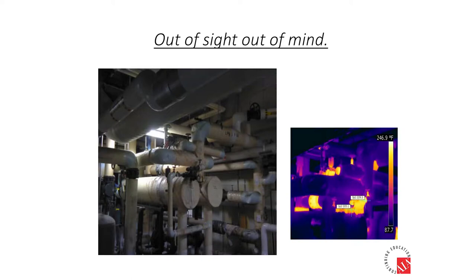And the reason I'm pointing this out is most of you people that have infrared cameras are walking around these rooms all the time. And if you walk around in these rooms and you see these bright yellow, white objects in a dark room, you know there's opportunity. And all these guys that are electricians that are walking around with infrared cameras, I say, look at other things while you're there. Look around. This room, it looks like it's well insulated. But in infrared, all the things that are not insulated pop out.